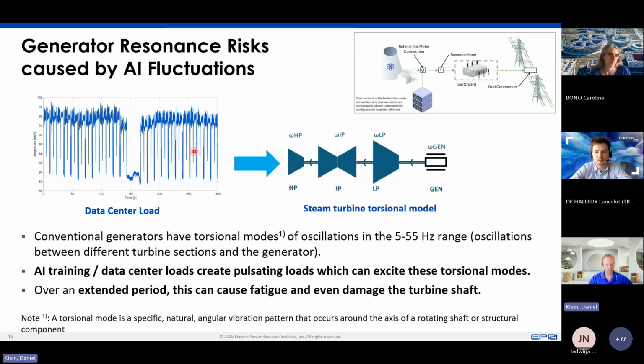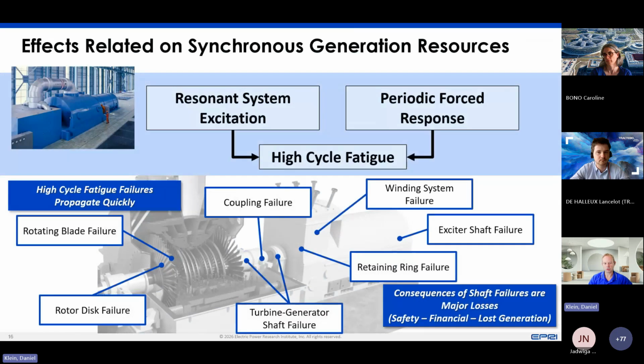Now with these fluctuating electric loads, they can excite a torsional mode. What that is, is basically a frequency range of that rotating shaft. A torsional mode is that specific natural angular vibration pattern that occurs around the axis of a rotating shaft. In other words, these fluctuating loads can hit the same frequencies that we have these torsional modes in various components, and that can lead to short-term or long-term fatigue.